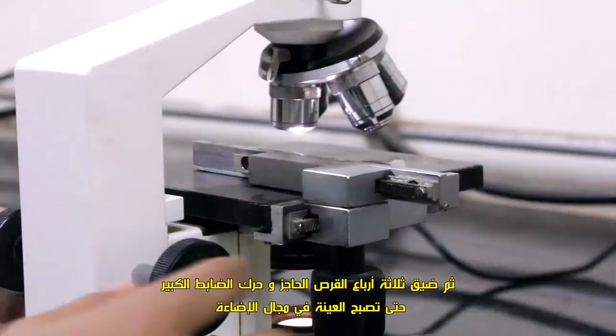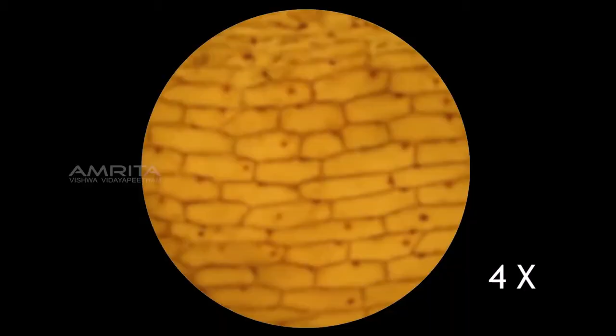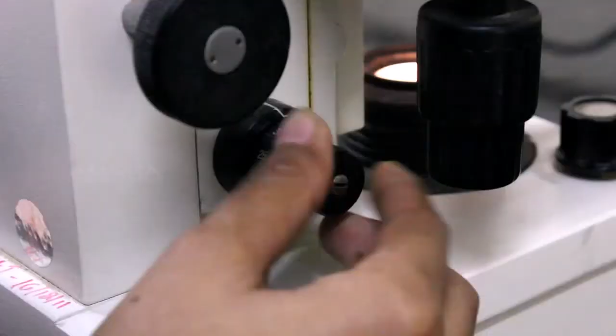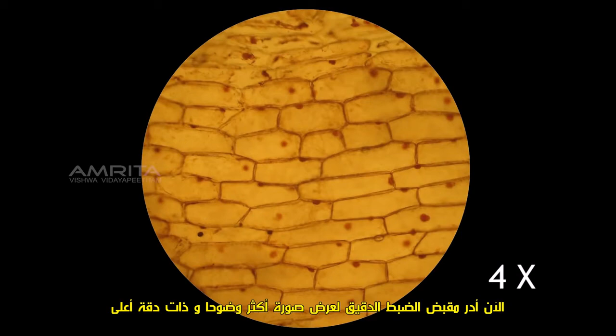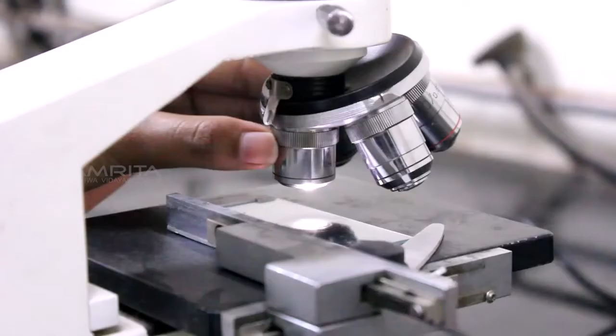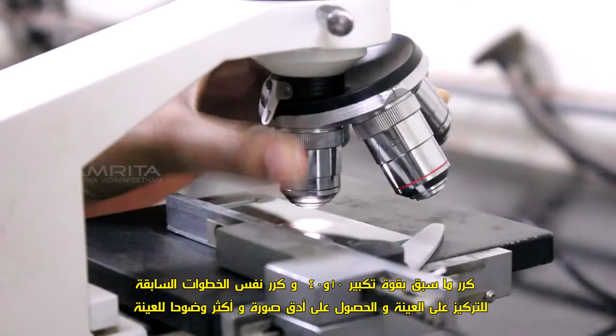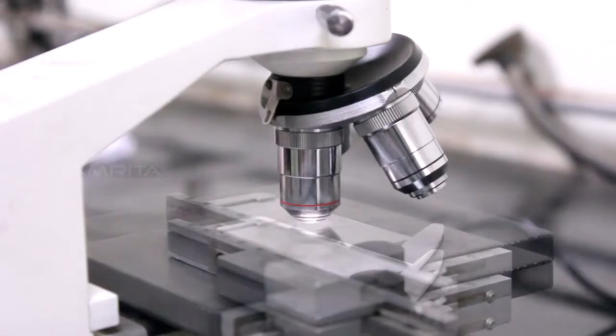Observe the sample through the microscope and adjust the iris diaphragm to the largest diameter to make the background brighter. Then close 3/4 of the iris diaphragm and adjust the coarse adjustment knob until the specimen is in focus. Now rotate the fine adjustment knob to view the image more clearly with good resolution. Again rotate the nosepiece to the 10x and 40x objectives and repeat the same steps to focus the specimen and to get a finer and clearer image of the sample.